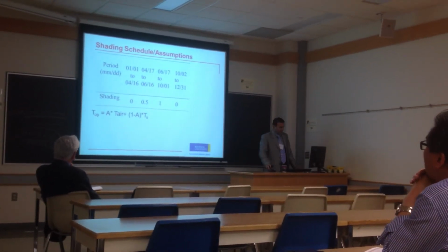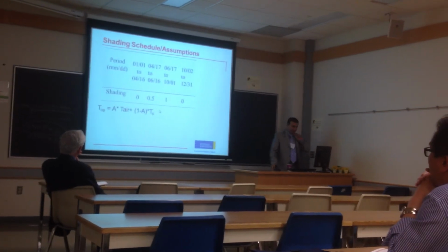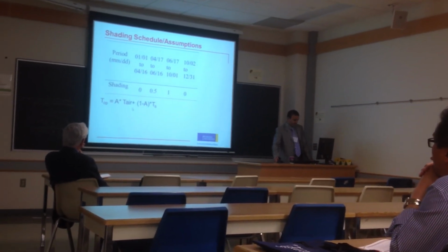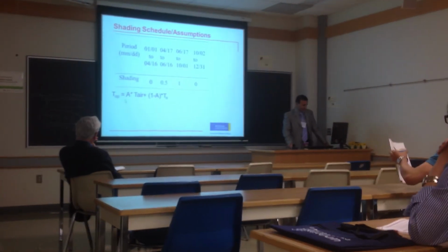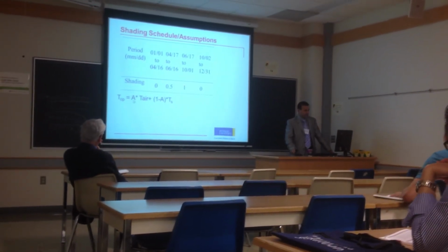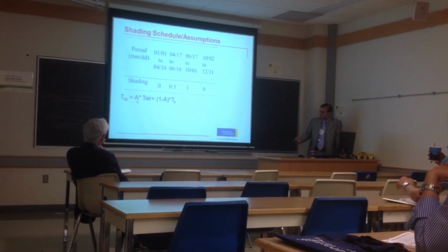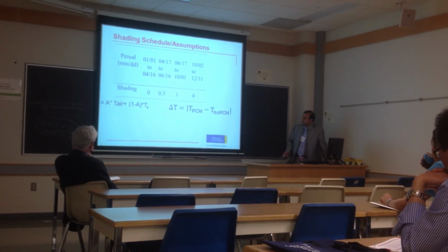So to analyze the temperature inside, I'm not taking temperature of the air inside, but I'm using operative temperature, which is more closely to the temperature that we are feeling. So temperature of the surface and temperature of the air, which is almost half here, can give you operative temperature.